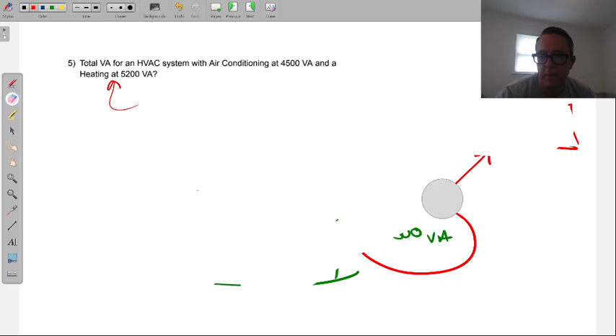I actually ran into this, and I think I mentioned it, it slowed me down for a second. I was like, wait a minute, do I have to provide two breakers for this one thing? But then I was like, no, wait a minute, it's a single unit. When you look at the nameplate information on the back of an air conditioner, it'll give you the heating and the cooling information, the pressures and all the heating elements and all that stuff. So it has both sets of information.